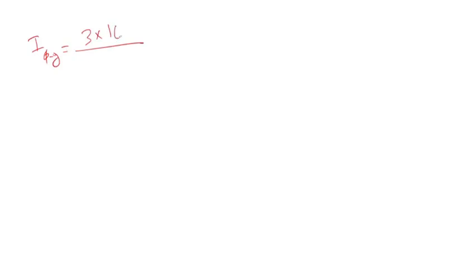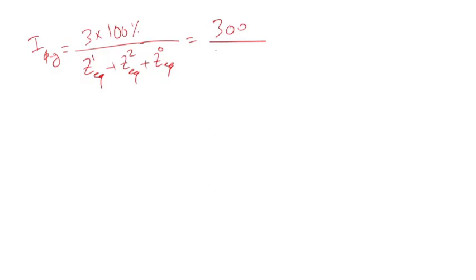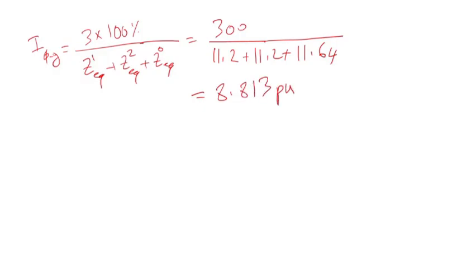The phase-A to ground fault — since I'm working in percent — is three times 100 percent divided by the positive equivalent impedance plus the negative equivalent impedance plus the zero sequence equivalent impedance. That's 300 divided by 11.2 plus 11.2 plus 11.64, which comes to 8.813 per unit. That is the phase-A to ground fault in per unit.